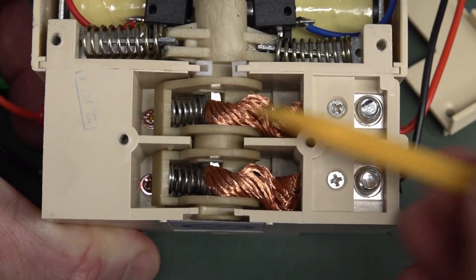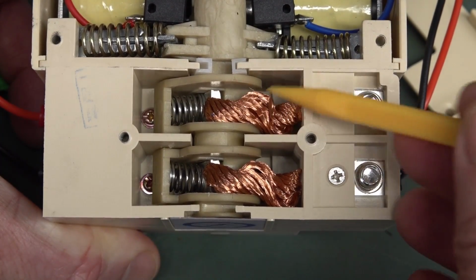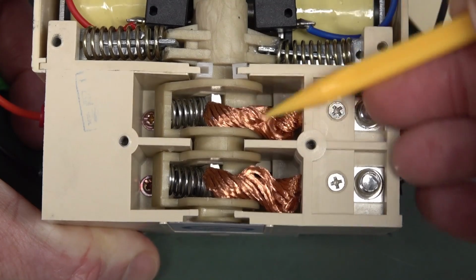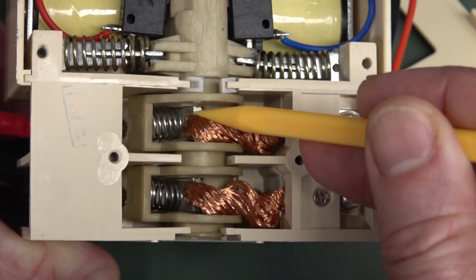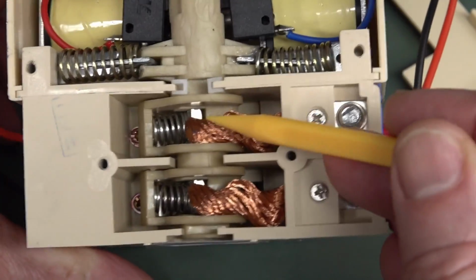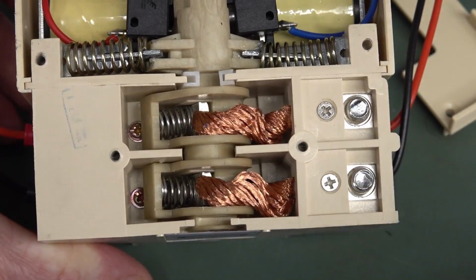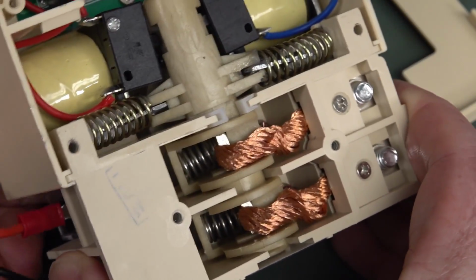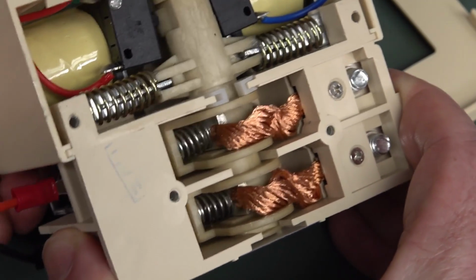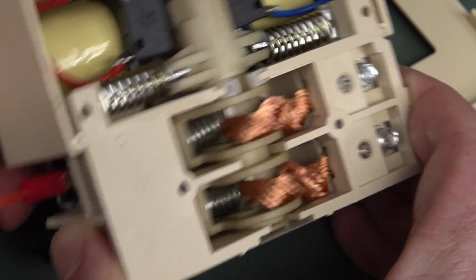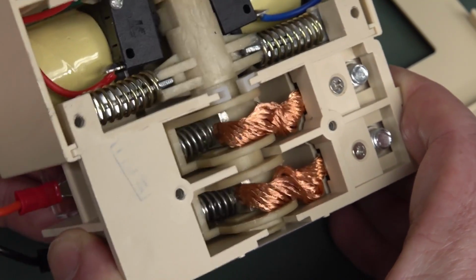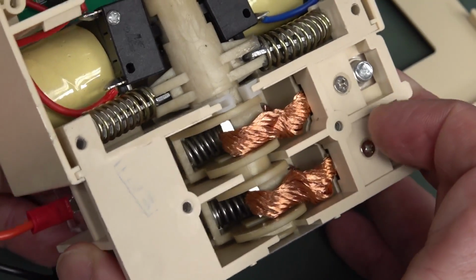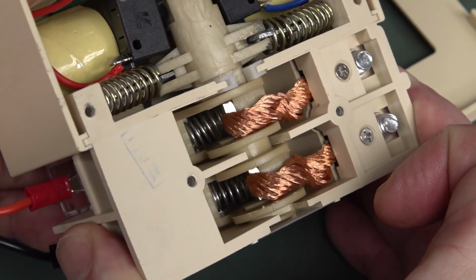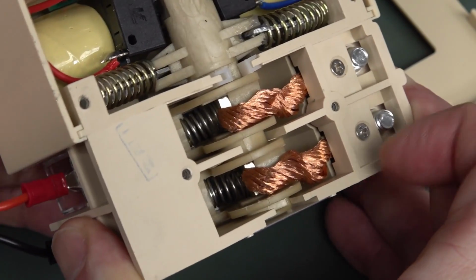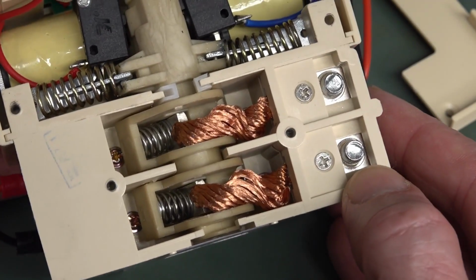This is interesting, check this out. This is the load output here, and they've got huge big braided connectors welded onto that plate, and I can't see how that goes down to the bottom side. The reason they do that is so you've got some compliance when that moves, because this is rated for, I think, 5,000 cycles. So when this moves back and forth, even though it doesn't move a lot, there's going to be stress in there, so that needs to expand and contract, and of course carry the maximum rated current as well.